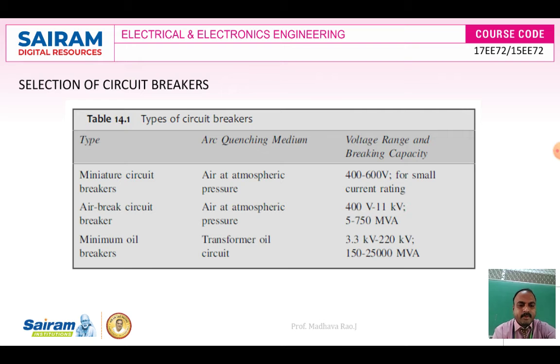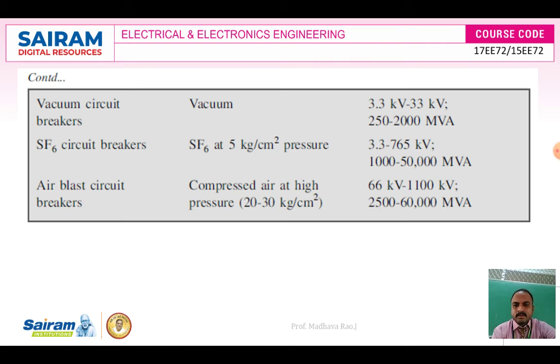You can see the power ratings also. The vacuum circuit breaker uses vacuum as the medium, and you can use it for the 3.3 to 33 kilovolt range. For SF6, the medium is SF6 gas, and you can use it for 3.3 to 765 kilovolts. For the air blast circuit breaker, compressed air is the medium, and you can use it for 66 kilovolts to 1100 kilovolts. We can also see the power ratings here, but power ratings are not that important for choosing the circuit breaker. The first preference we have to give is the voltage, right?